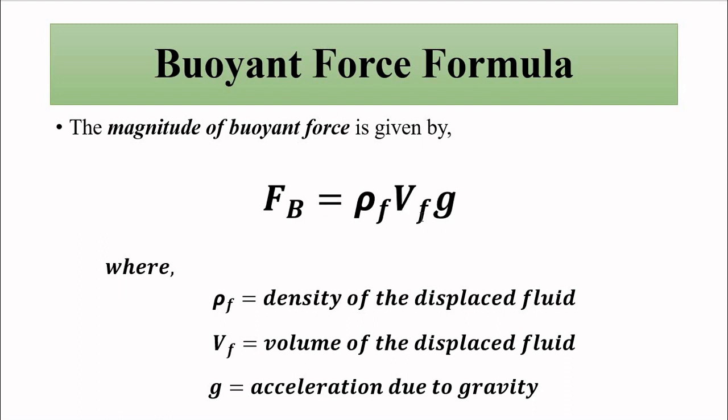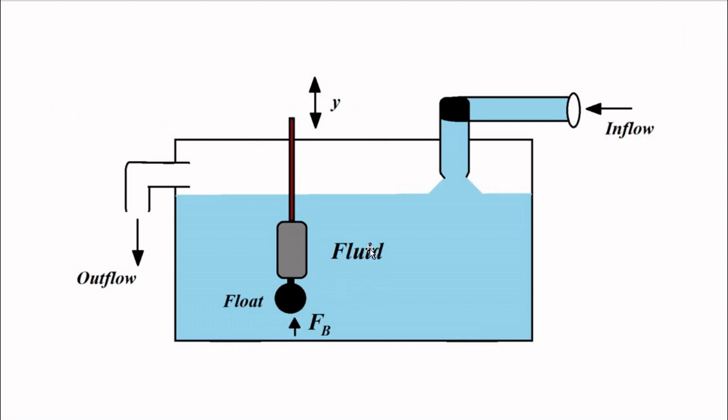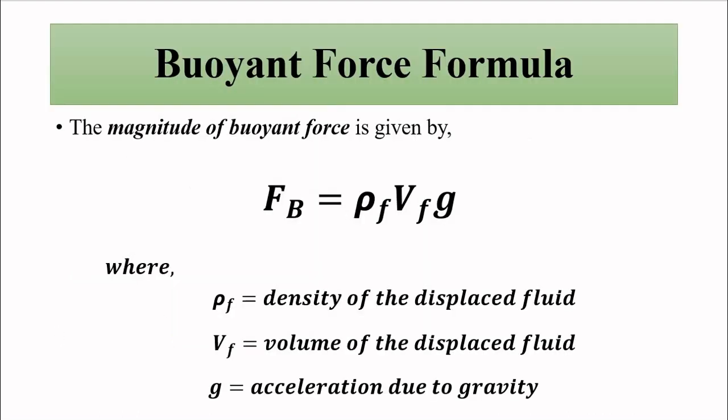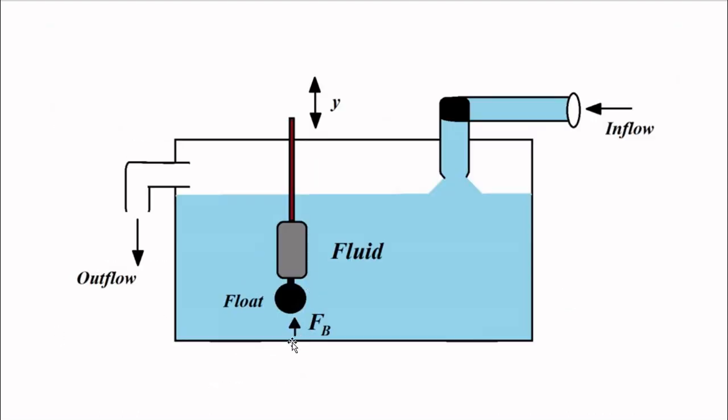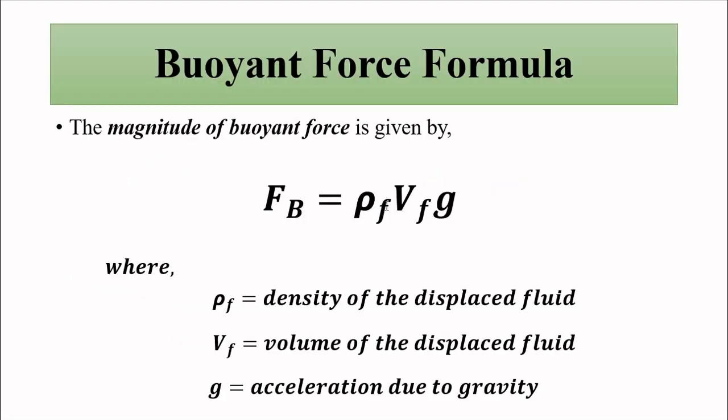That scale is calibrated directly in terms of density. Because V_f is fixed, g is fixed, this buoyant force is directly dependent on the density of the fluid. No matter whichever fluid is there in this container which is measured, volume of the fluid that is displaced will be fixed because of the fixed size dimensions of the float. Also, the acceleration due to gravity is fixed. The buoyant force which acts because of the displaced fluid is directly dependent on the density of the fluid.